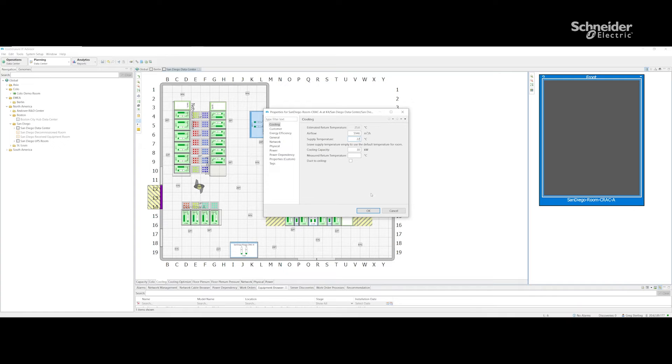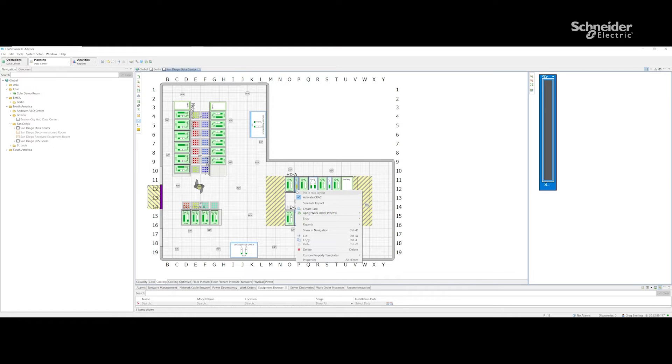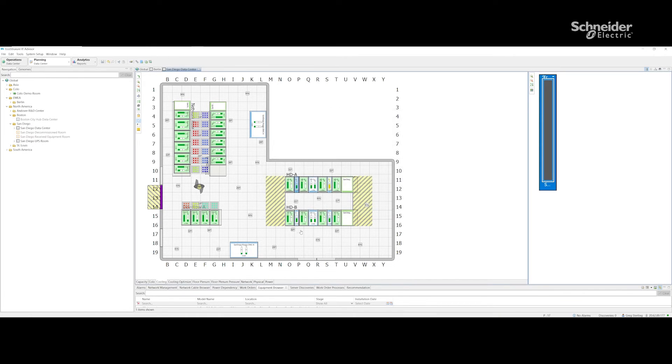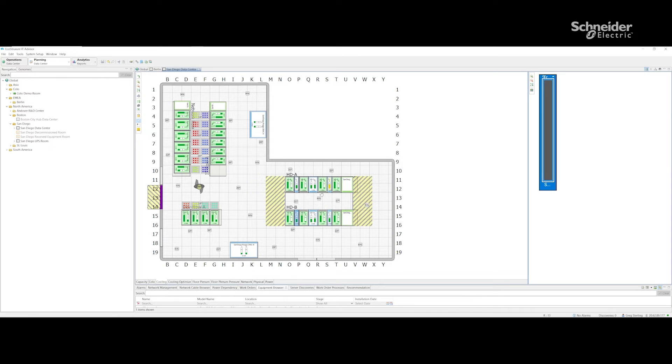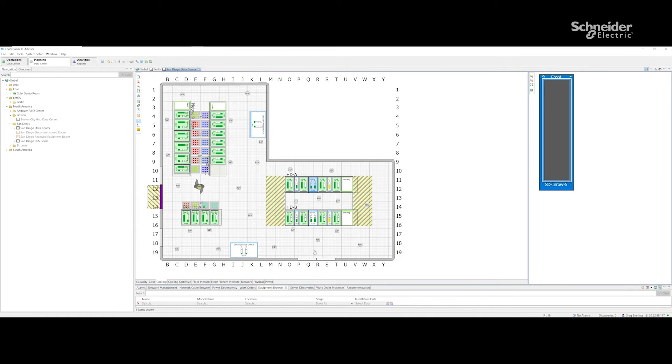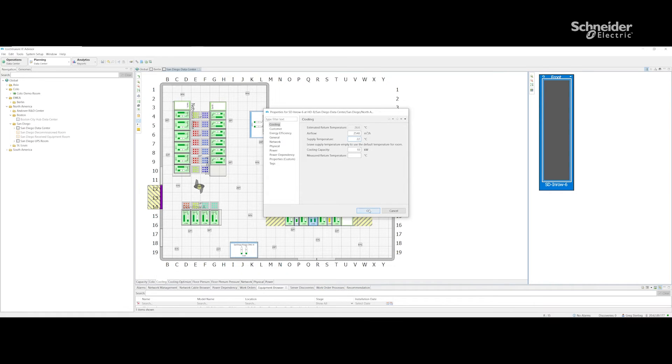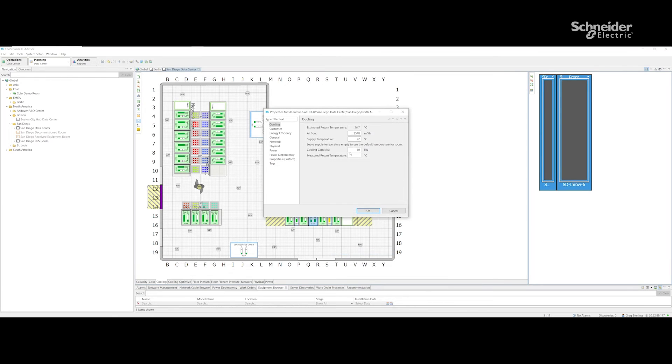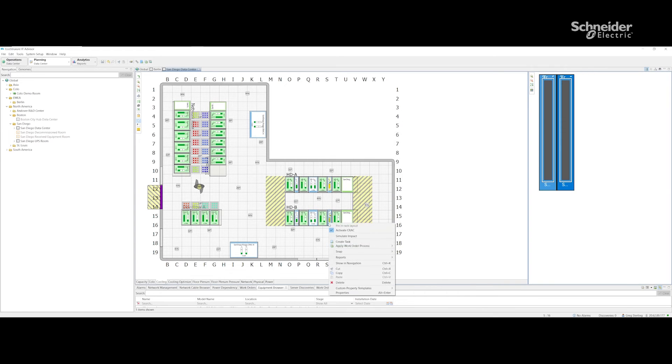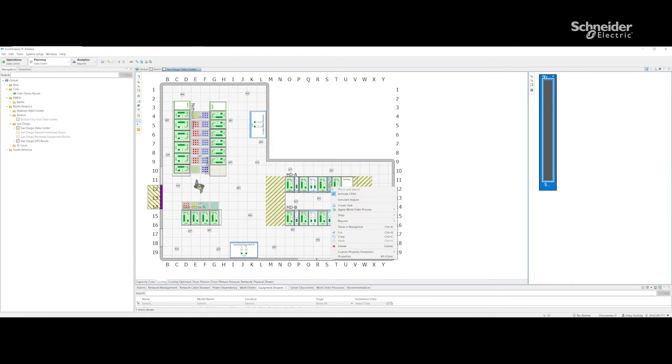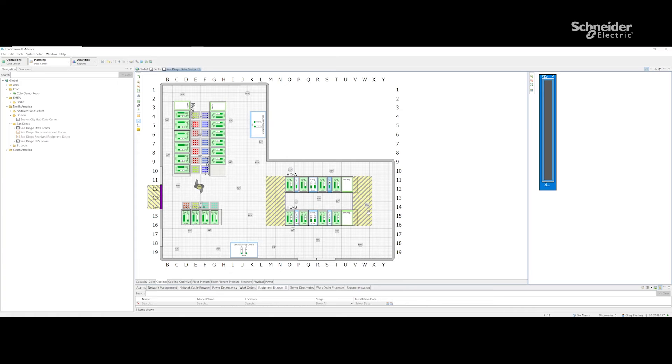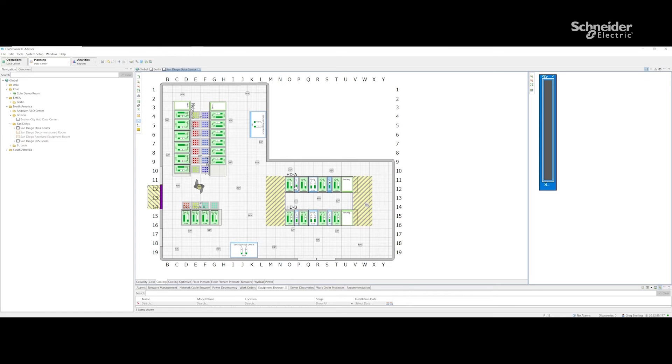As I change the supply temperature, you'll notice the temperature in the racks is increasing. There's that green bar on the rack, and some cooling units are being stressed less or more depending on which unit is being set up with the new supply temperature. Now we've changed the supply temperatures for every cooling unit inside our room to 22 degrees.